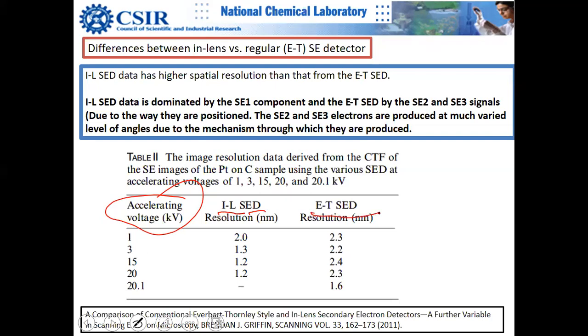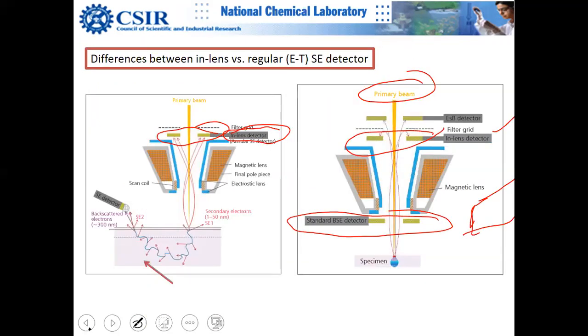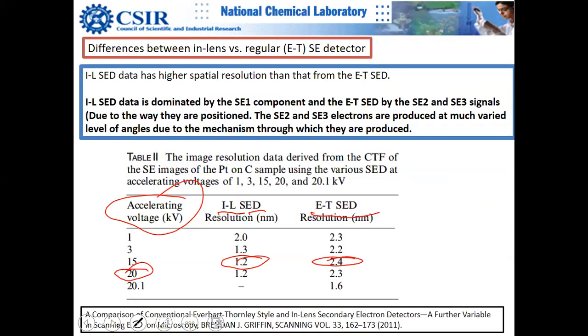With an in-lens secondary electron detector, for example at 20 kV, the resolution is almost twice as good as with the Everhart-Thornley detector. SE2 and SE3 electrons coming from larger areas reduce resolution. In-lens design excludes these unwanted signals — SE2 and SE3 worsen the resolution in the ET detector.